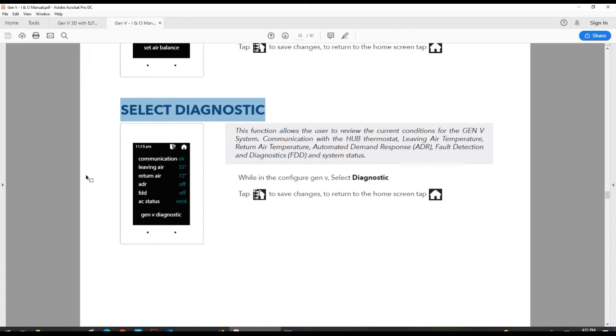From the Gen V control system, from the hub thermostat, you can go in and look at the Gen V controller and confirm its operation. So you can confirm it's communicating with the hub thermostat. You can check your leaving and return air temperatures. If you're using the ADR FDD features, they will tell you if they've been energized or on, and then it will also tell you the status of the Gen V controller if it's in vent, heating, or cooling, or in changeover. So you can confirm that all from the hub thermostat without having to visually go check the control system.